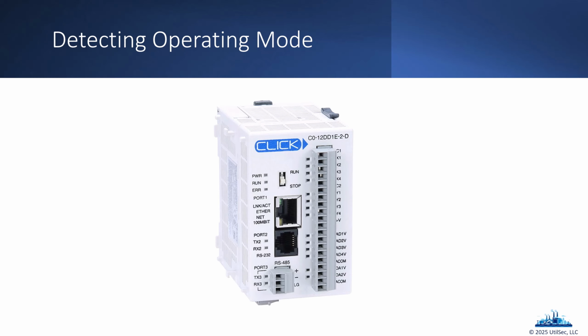But that's the idea. Now, of course, more expensive controllers actually have a physical key switch that you would insert in, and you could actually turn that. And then, of course, you could take that key out and lock it up. And then maybe only the plant manager has access to the key. And then you would have to get the key from the plant manager before you would be able to take it out of run mode to make any changes.